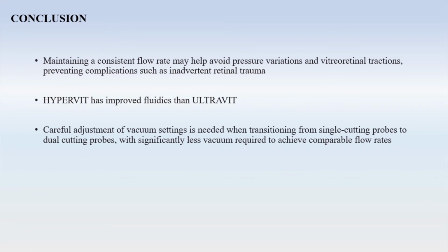So to conclude, the hypervit had improved fluidics in all the aspects. When we increased the flow rate, the other things like pulsatility and turbulence were less. So we can consider it for the future in vitrectomy. That's all. These are my acknowledgements.